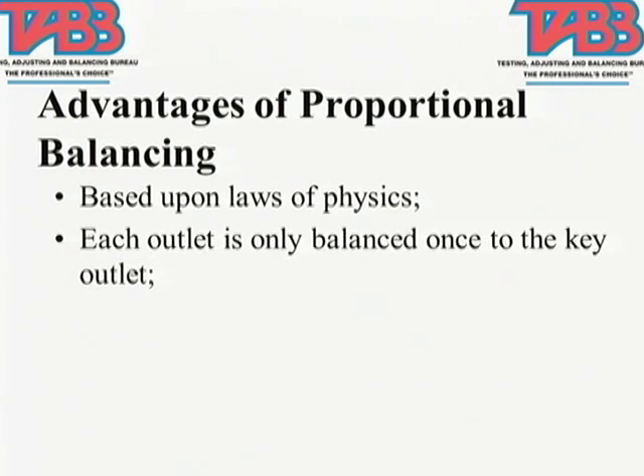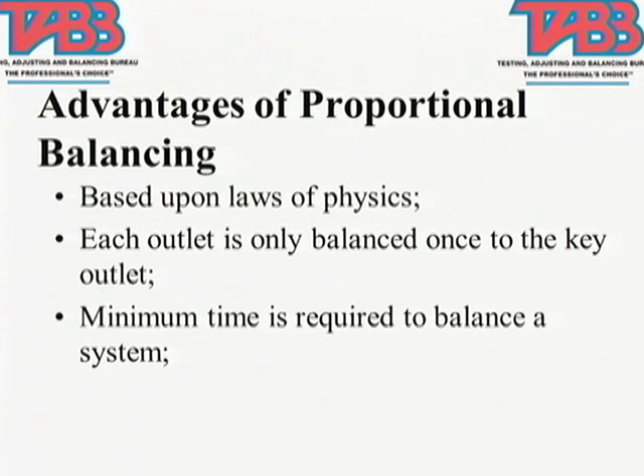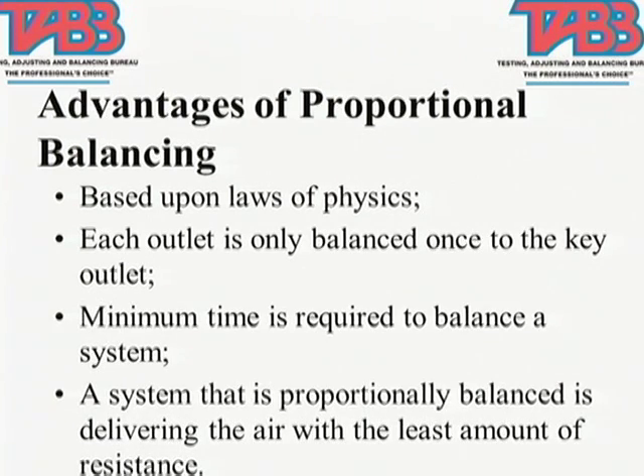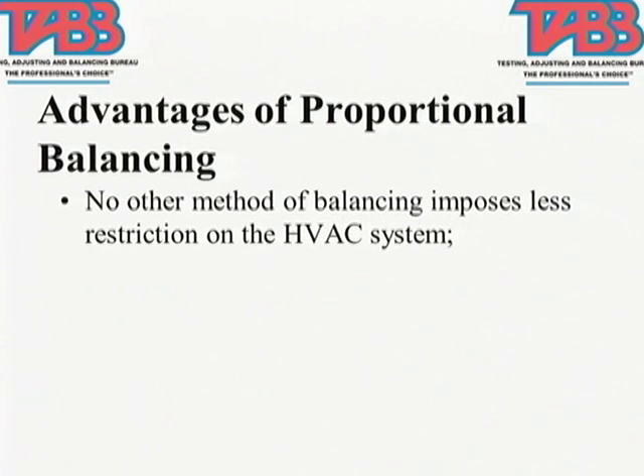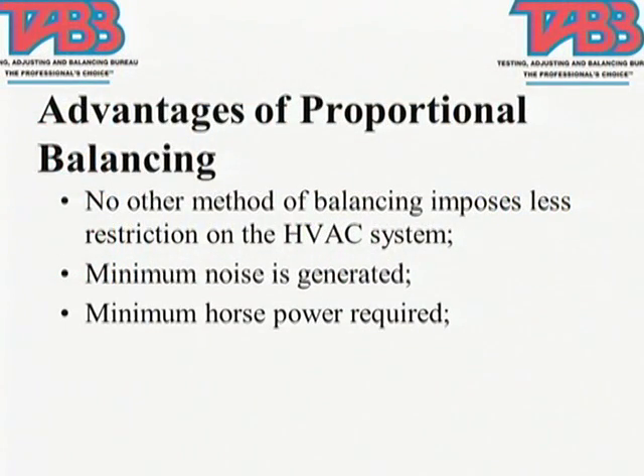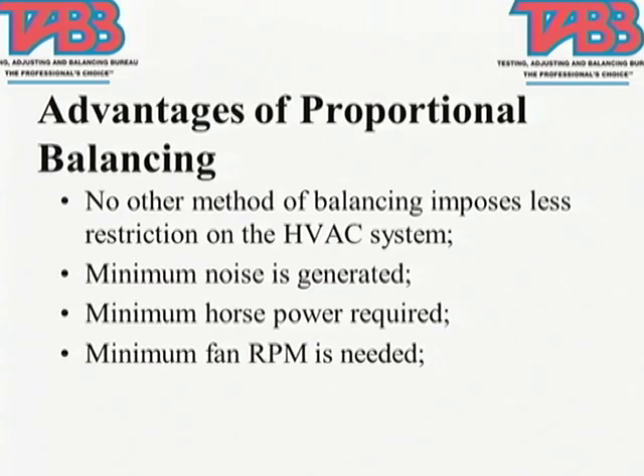Advantages: it's based upon laws of physics. Each outlet is balanced once. Minimum times required. All systems that are proportionally balanced will be delivering the air or water with the least amount of resistance. No other method imposes less restriction on the HVAC system. Minimum noise, because if you can imagine, when you start cranking on dampers and valves, we immediately start saying when we put too much on, we build a static pressure up and velocity pressure is going down, we start to generate noise. Minimum horsepower is required. Minimum fan RPM is needed.